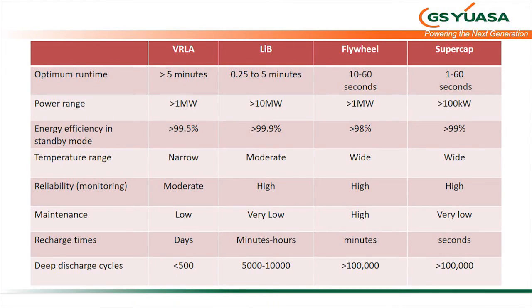you're lost. Whereas if you've got 30 seconds or a minute, you've got two or three times to get the diesel generator running. Or you could be thinking about it and maybe not triggering immediately. If you've got a supercap, you're going to have to hit the diesel generator button as soon as you lose power. At least with lithium ion, you've got the chance, 5 seconds to think about it before you start putting actions in place. So they're the sort of time scales, the power ranges which are available now. Lead acid, you've got one megawatt power ranges. There's more than megawatt sizings out there at the moment. Lithium ion batteries, I think 20 megawatts is the biggest that we've fitted at the moment as a system. Flywheels, probably around a megawatt area. Supercaps, I'm not aware of any more than about 100 kilowatts.